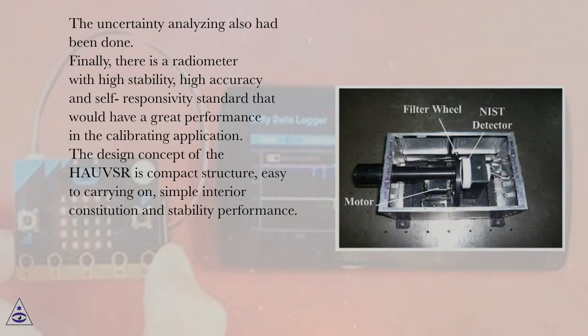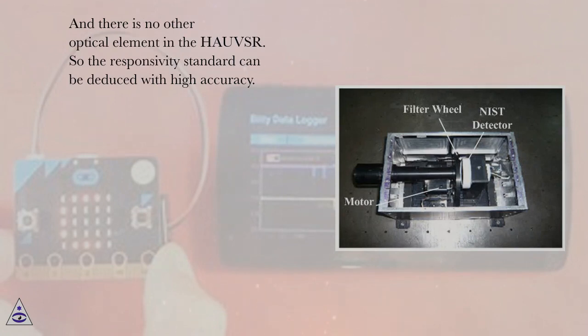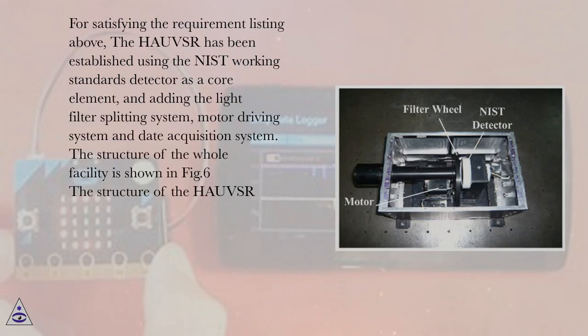The design concept of the HAUVSR is a compact structure, easy to carry, with a simple interior constitution and stable performance. There are no additional optical elements in the HAUVSR, so the responsivity standard can be deduced with high accuracy. To satisfy these requirements, the HAUVSR was built using the NIST working standards detector as a core element, with a light filter splitting system, motor driving system, and data acquisition system. The structure of the whole facility is shown in Figure 6.